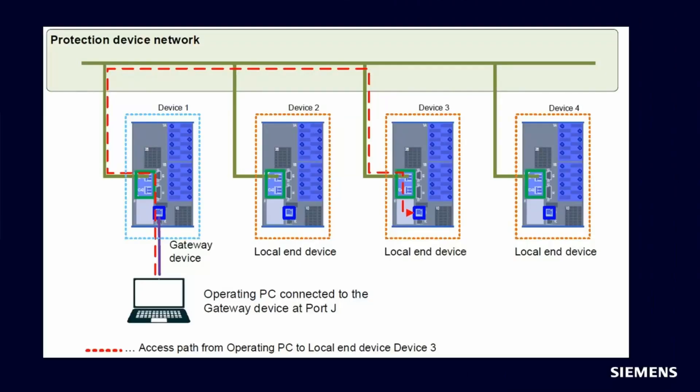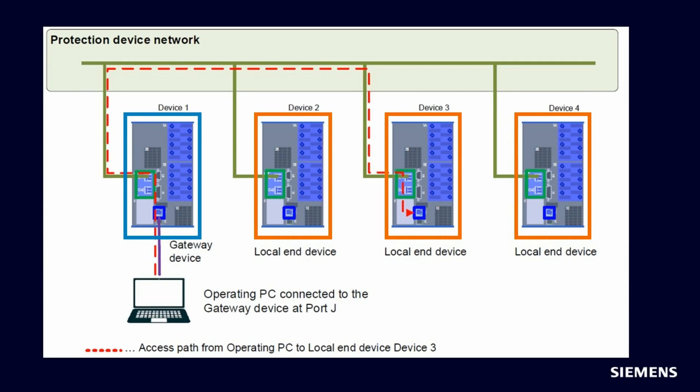With the routing manager functionality, it is possible to access via one gateway device to several local end devices. The gateway and all local end devices must be connected into a protection device network. This protection device network can, for example, be the process bus network which is used for the distributed bus bar protection.